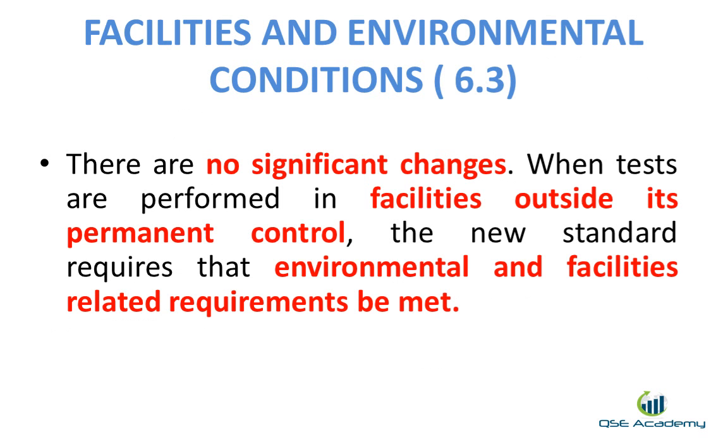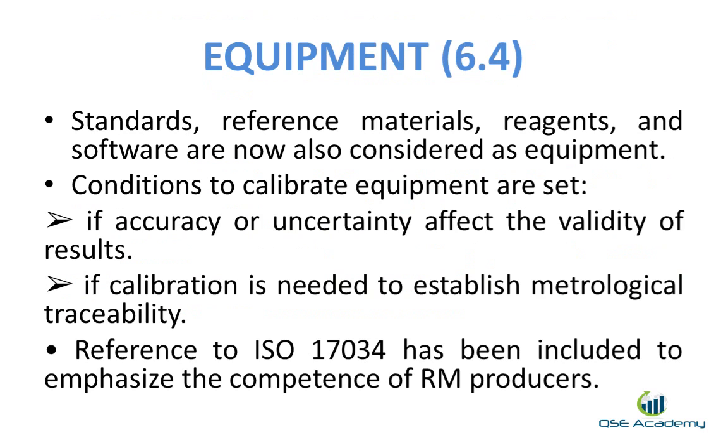Facilities and environmental conditions. 6.3. There are no significant changes. When tests are performed in facilities outside its permanent control, the new standard requires that environmental and facilities-related requirements be met. Equipment 6.4. Standards, reference materials, reagents, and software are now also considered as equipment.